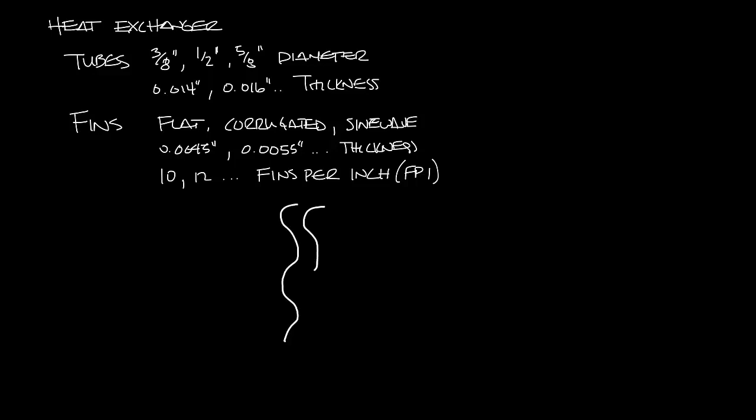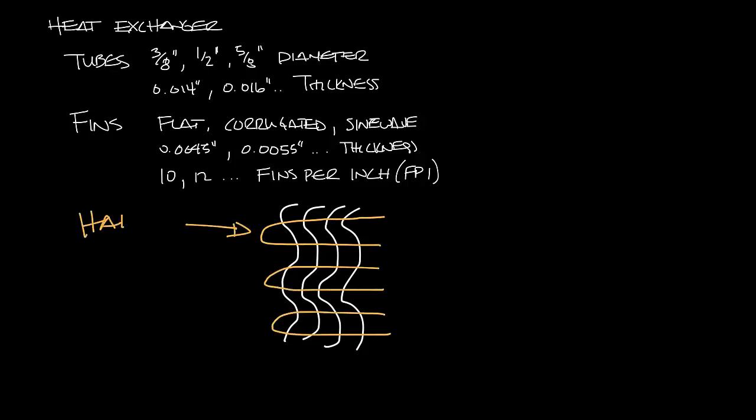So let me draw the fins. I am not so great at drawing sine waves apparently, but let's say these are fins in a water coil. The copper tubes are bent into hair pins and inserted through the fins, and then each hair pin is connected on the opposite side with a return bend that's welded on so that you get continuous flow of water through the tubes.